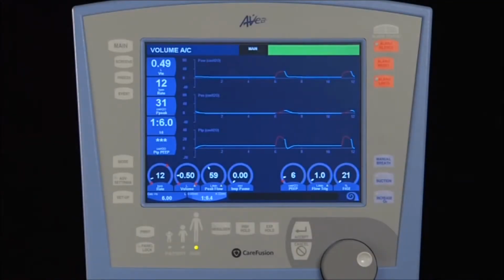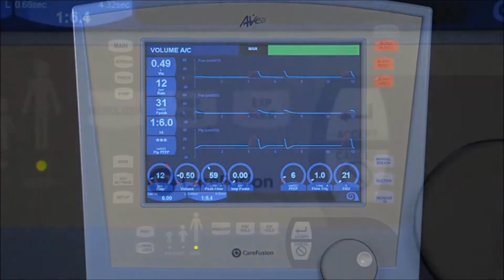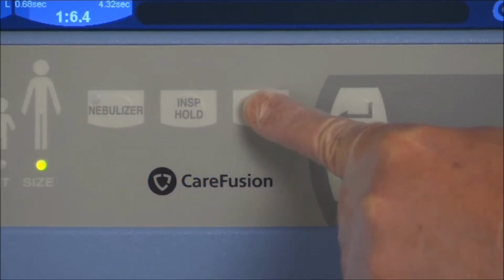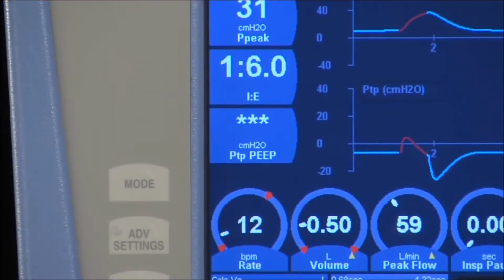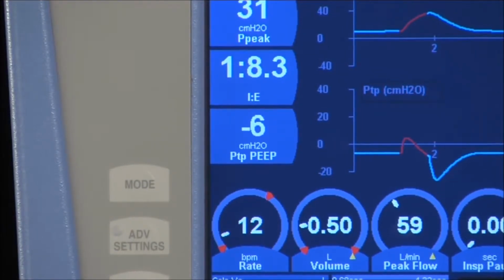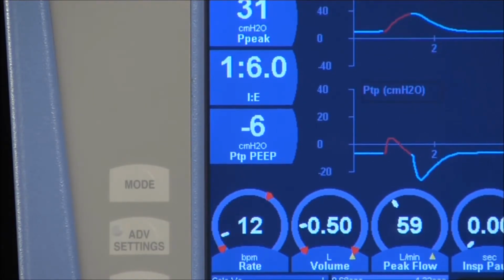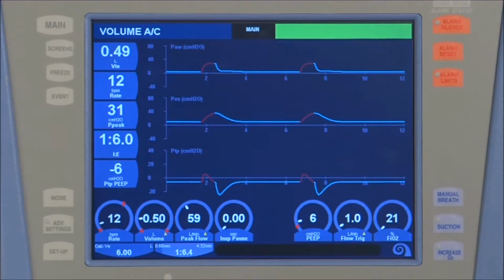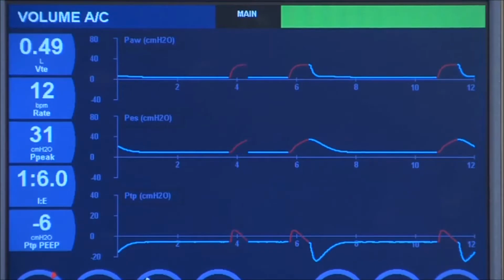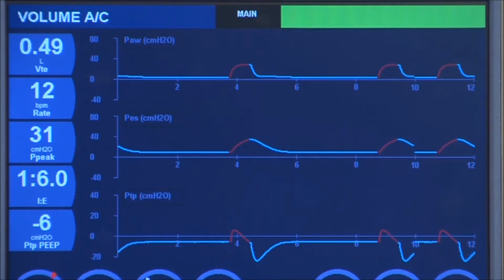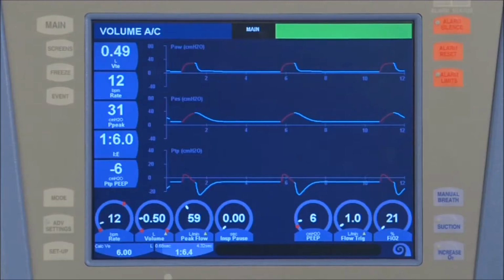To obtain a transpulmonary PEEP, the operator depresses the expiratory hold control until a static baseline is observed. Repeat the maneuver to confirm reproducibility. Transpulmonary PEEP gives the clinician guidelines for PEEP setting and allows the operator to adjust the settings that improve baseline inflation in clinical situations where the chest wall compliance may influence ventilating pressures. Normal transpulmonary PEEP pressure is around 0 centimeters water. A negative transpulmonary PEEP pressure may indicate that a patient's PEEP setting could be increased to provide better ventilatory support.